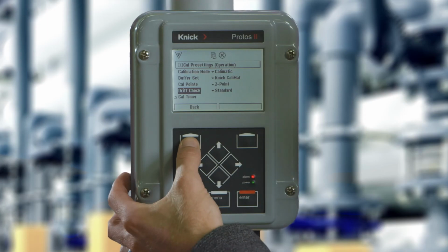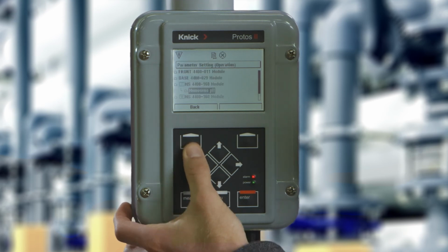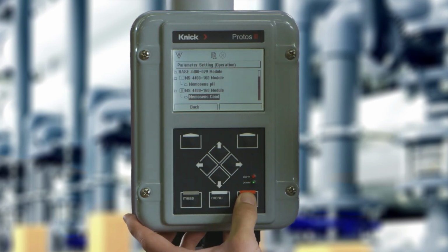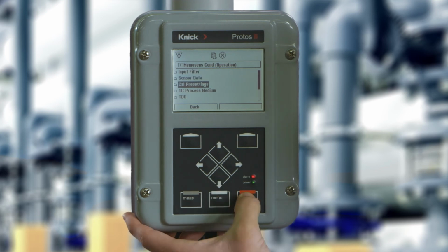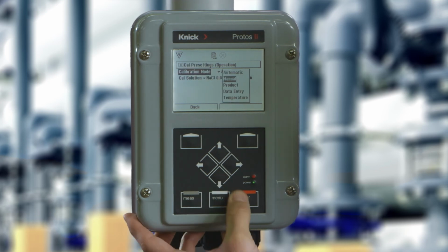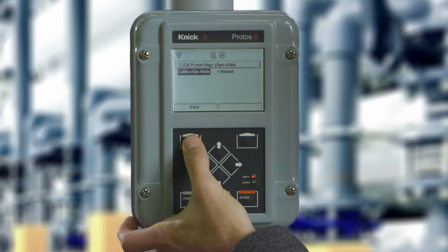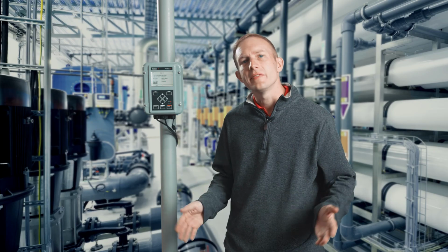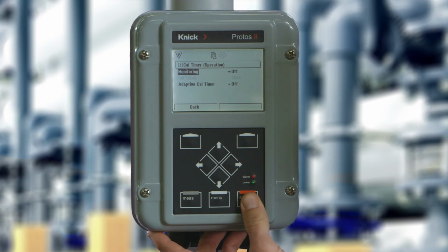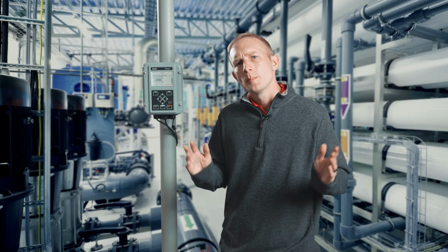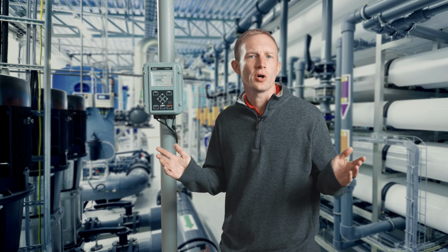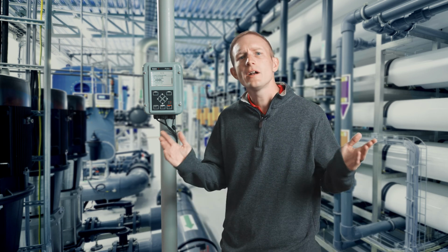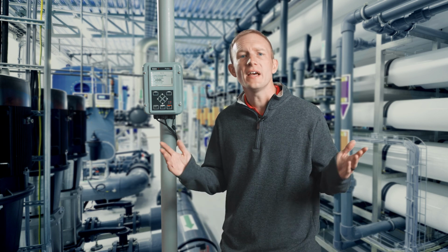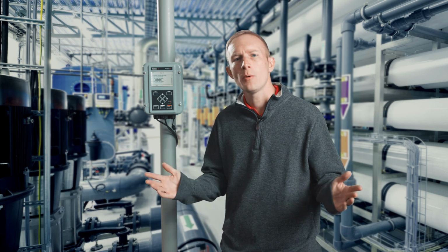Repeat the process for the conductivity sensor on channel 2, this time selecting manual for the CAL mode. Lastly, the calibration timer allows us to set either a fixed interval or an adaptive evaluation based on the sensor loads for indication that a calibration is needed. Please remember that we are configuring the default calibration settings. The settings can always be changed by the operator at the beginning of any calibration procedure within the CAL menu.